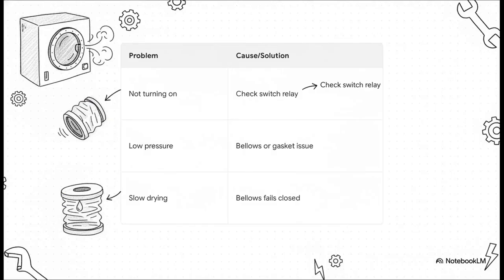But things in the real world do break down. And when they do, clinical techs basically have to play detective. For instance, if those instrument packs are coming out wet and taking forever to dry, the tech instantly knows the bellows likely failed in a closed state, which traps all that excess moisture inside instead of letting it escape. Or, if the machine isn't fully pressurizing, that's a dead giveaway to check the door gasket for leaks.